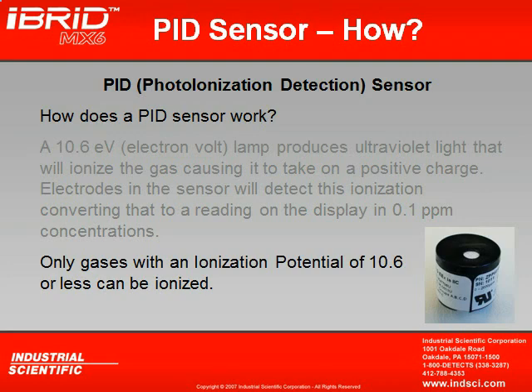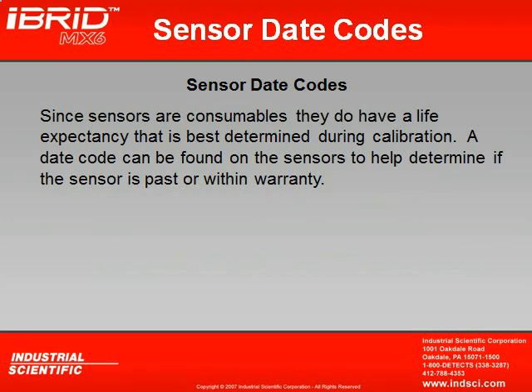Since sensors are consumables, they do have a life expectancy that is best determined during calibration. We never want to try to time change out our sensors or battery packs. Rather, we want our calibration to determine when these sensors ought to be changed out. But there are date codes on the sensors that can help us determine if the sensor may be within or past its warranty. So when we're looking at the catalytic diffusion sensor, remember this is your LEL sensor, if we want to read the date code of the sensor to see when the sensor was actually manufactured, we're going to use the serial number, and it reads year and month of make. So in this example, we see the first four numbers of the 0701. That would indicate to us that the sensor was made in 2007, first month. So that'd be a January 2007 make.